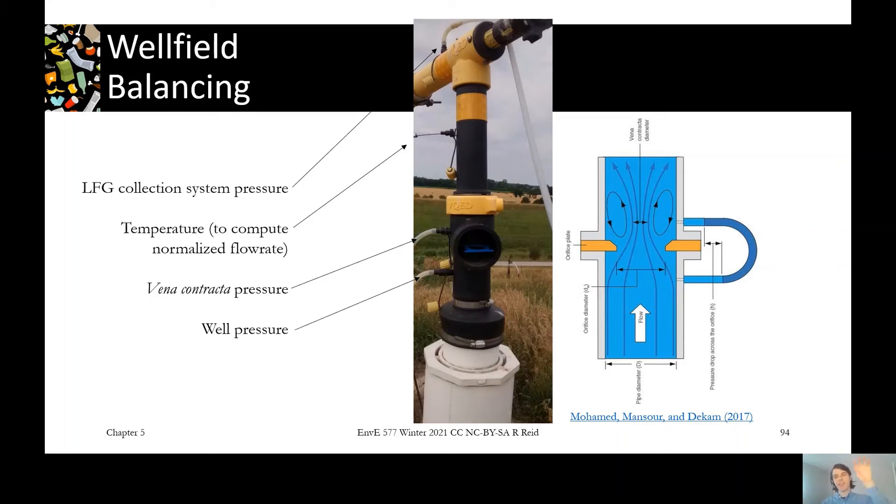And then at the very top, we have a port that measures the pressure on the blower side of the valve. So this is before the pressure would be decreased by being forced through the constriction of the valve. And that tells us how much pressure is available at this location. So if the valve was open 100%, then this pressure would be very similar to the pressure a little bit down the wellhead. But as that valve's closed more and more, then the pressure between them becomes different.